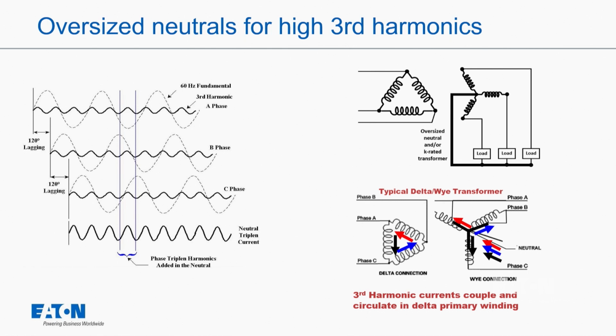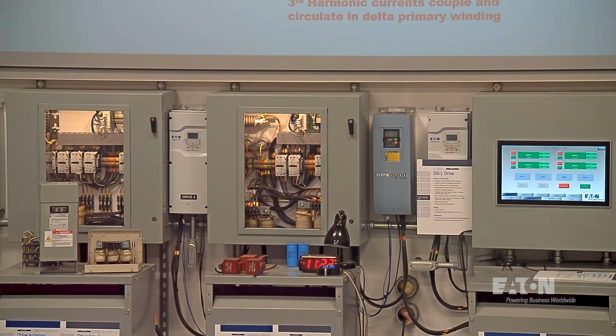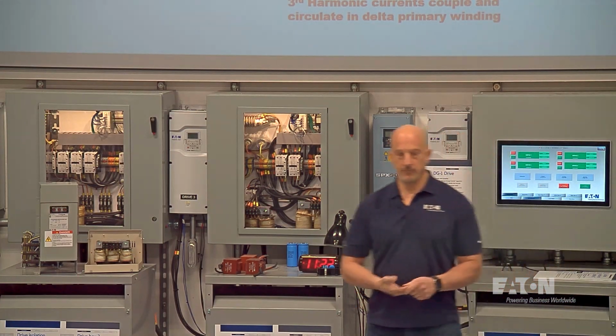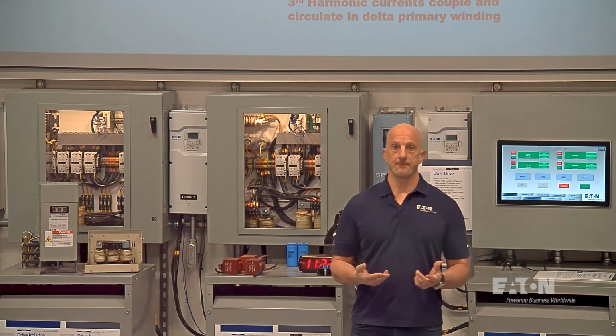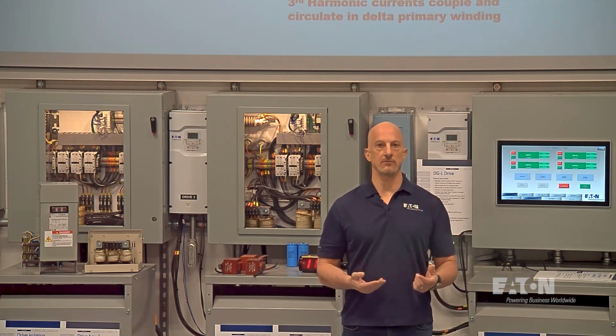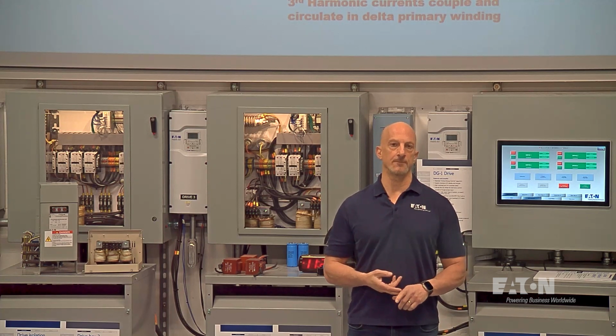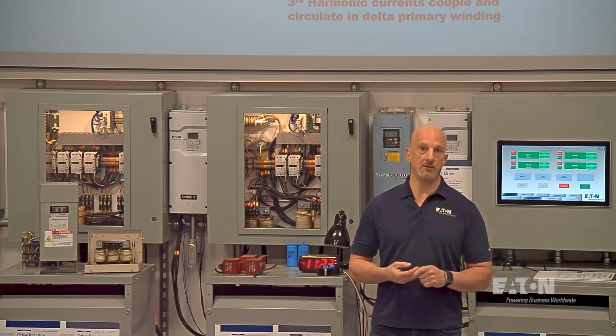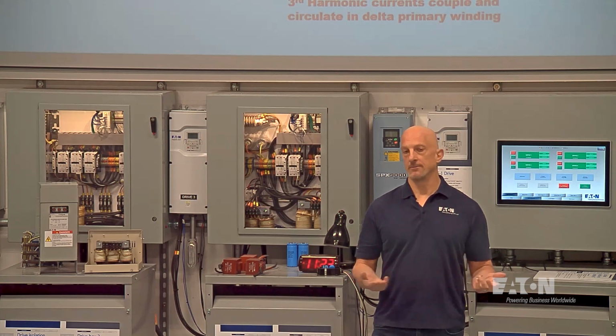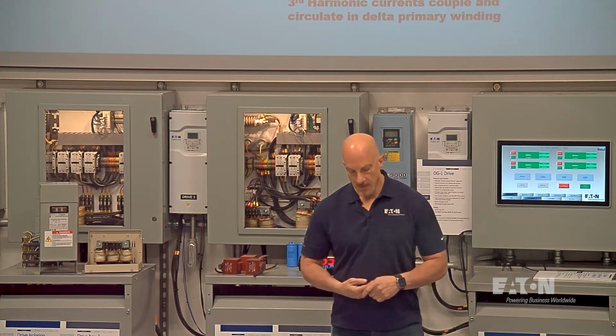And a lot of times on a K-rated or harmonic mitigating transformer, that will already be the case. But again, a simple answer is, if you have a lot of third harmonics, you have to consider oversizing the neutral in your panel board. If you're going to have three-phase loads, you probably don't have to.